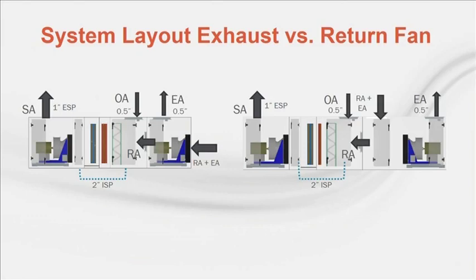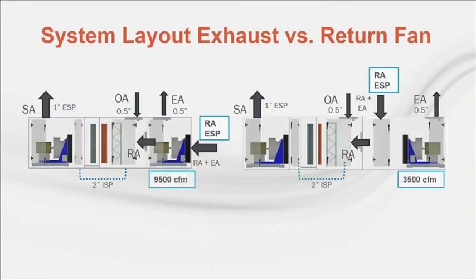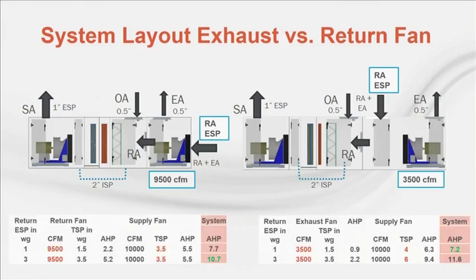Which system requires more air horsepower will vary based on the return static pressure. The two differences are that in the return fan system, the relief fan is penalized as it sees more airflow — 9,500 CFM versus 3,500 CFM in this example. The other difference is the exhaust fan system supply fan is penalized as it sees more static pressure. At low return static pressure of 1 inch, the air horsepower removed from the supply fan by the return fan is less than the air horsepower added to the return fan. So the system requires more air horsepower from the fans to use a return fan.